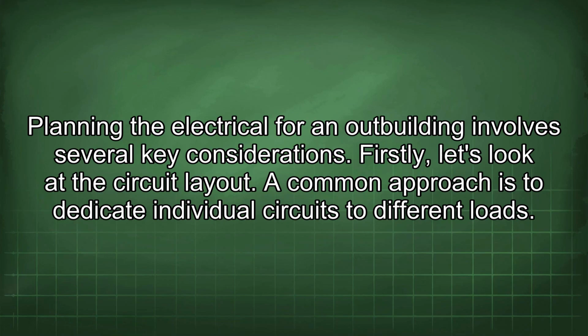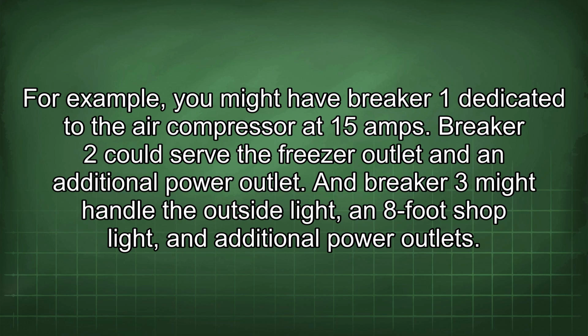Planning the electrical for an outbuilding involves several key considerations. Firstly, let's look at the circuit layout. A common approach is to dedicate individual circuits to different loads. For example, you might have breaker 1 dedicated to the air compressor at 15 amps. Breaker 2 could serve the freezer outlet and an additional power outlet. And breaker 3 might handle the outside light, an 8-foot shop light, and additional power outlets.